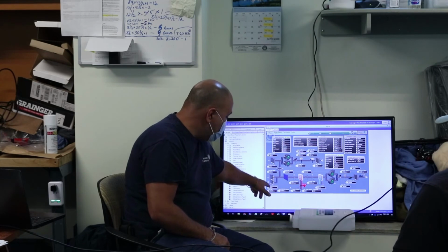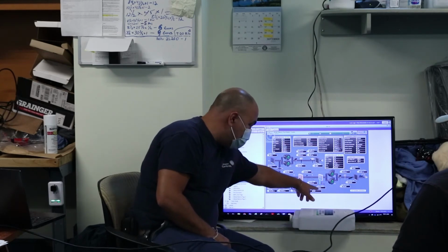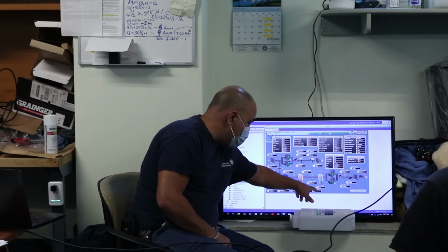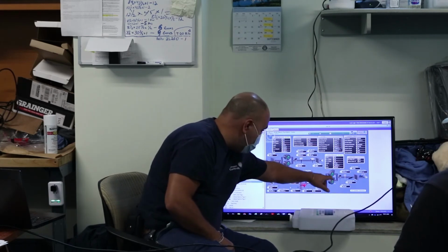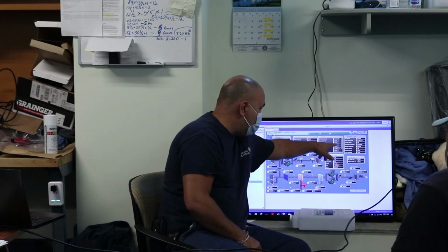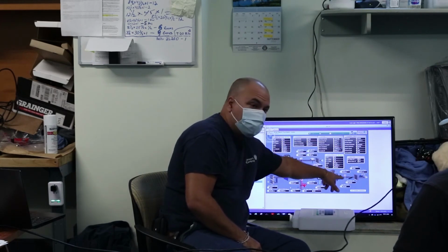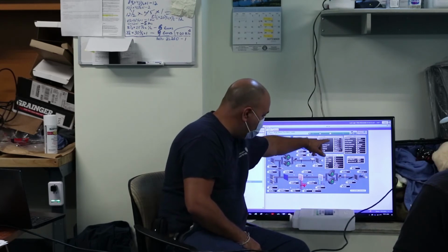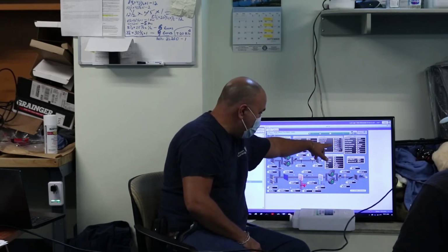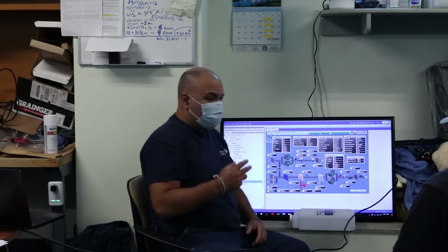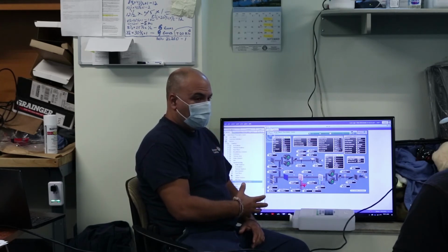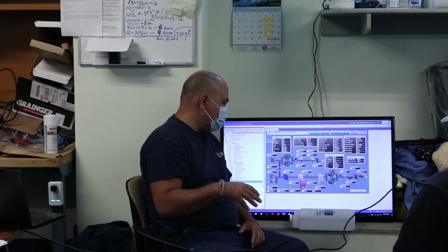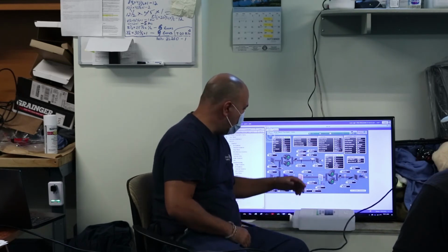But now you have full outside air, and the second stage is now a cooling valve. So you have the outside air and the cooling valve open to maintain. We're looking for 58 degrees, and we're doing 57.6 right now. Again, yesterday we touched on the set point control. We're in automatic, so the DAT is going to reset based on your VAV box positions. It's like half a degree every half hour, I believe.